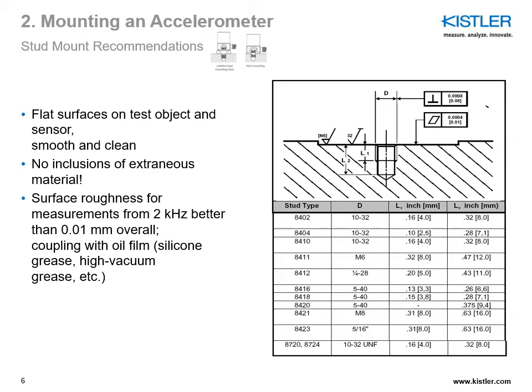Whenever stud mounting the sensor, the coupling surface must be as smooth, flat, and clean as possible. With higher frequencies from about 2 kHz, it is beneficial to also have a thin film of oil or grease between the coupling surfaces. The tightening torque of the sensor is usually very critical — you should use a calibrated torque wrench of suitable design. Before mounting the sensor, if you are doing a mounting where isolated studs are required, you always need to check that stud for damage.